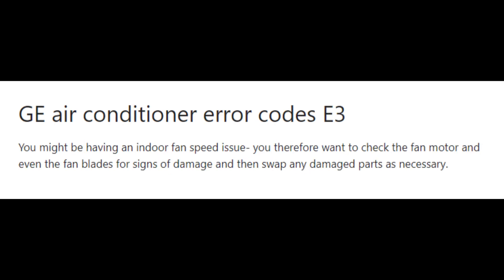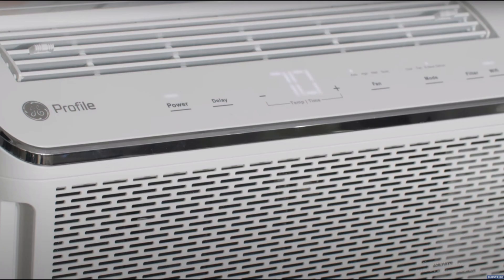Error code E3 indicates a problem with the indoor fan speed — the indoor fan speed is not being measured correctly. Check the fan motor and also check whether the fan blades are working properly, whether they are damaged or blocked. You may need to change the fan blades or even the entire fan motor if this error persists. If the error code continues, you may need to change the entire fan setup.